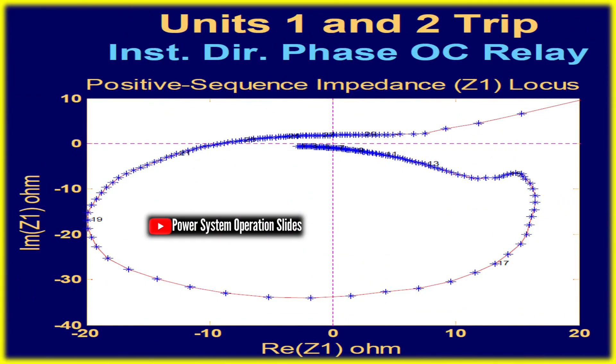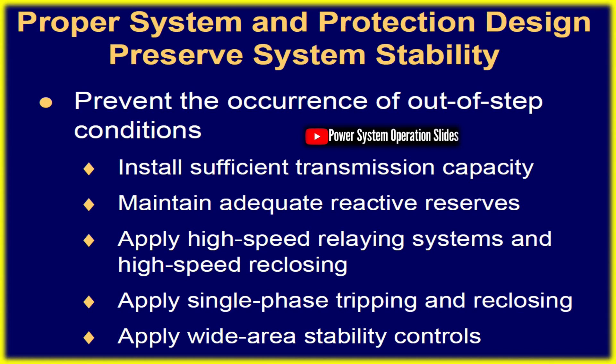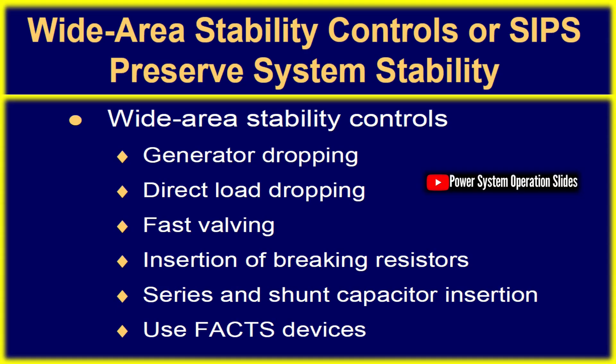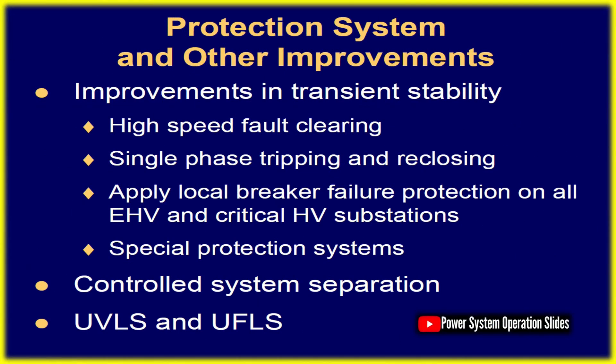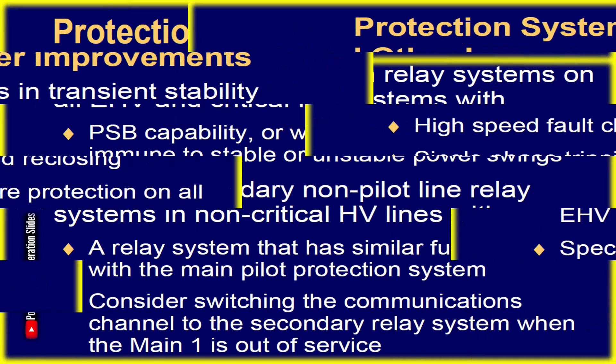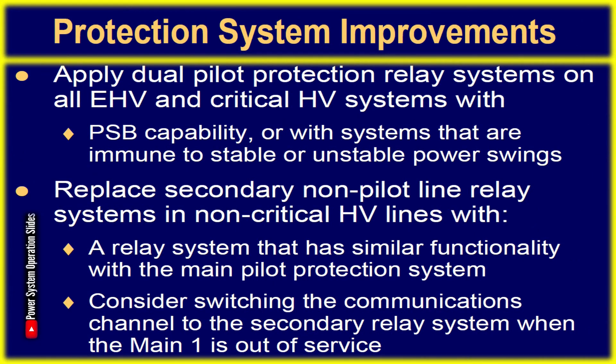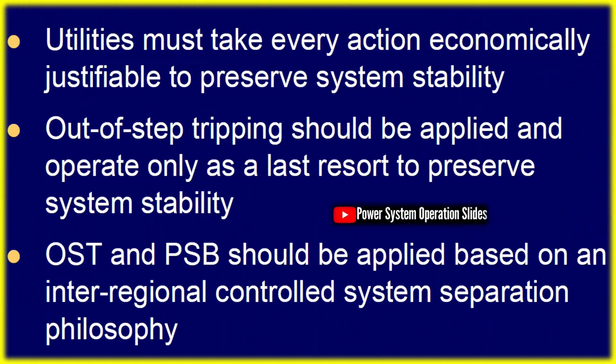Detecting an OOS condition typically involves analyzing apparent impedance at the generator terminals. Transient stability studies determine whether a generator can retain synchronism under various contingencies. During an OOS event, the impedance shifts reflect voltage and angular differences. When system sources are in phase (0 degree angle difference), generator terminal voltage peaks while current remains low. In contrast, when fully out of phase (180 degrees apart), voltage drops to a minimum while current spikes. To distinguish OOS conditions from actual faults, protection devices analyze the rate of voltage, current, and impedance changes. Fault conditions cause near-instant impedance shifts within milliseconds.